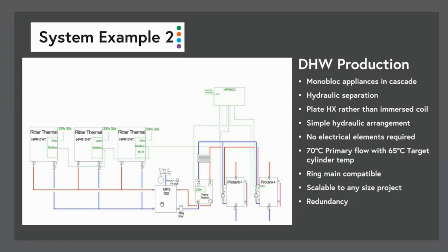This is the 100-litre buffer tank with your filling loop and expansion vessel and all the things required for a closed loop. So we're potable water on this side being circulated from the tanks to the heat exchanger, and we're a closed treated system, pressurized loop on this side. So the volume of this system here is fixed. It doesn't change. It's filled up and then sealed, and the water just circulates around. And then the load is shared across the appliances.